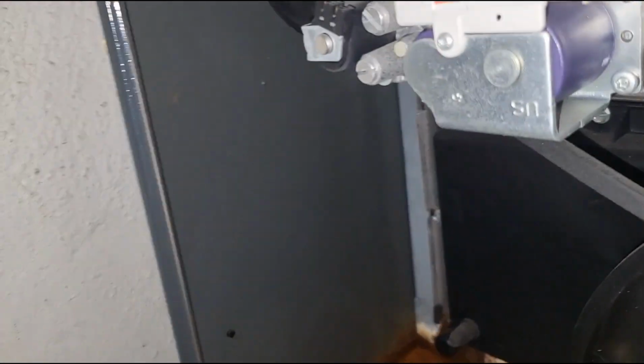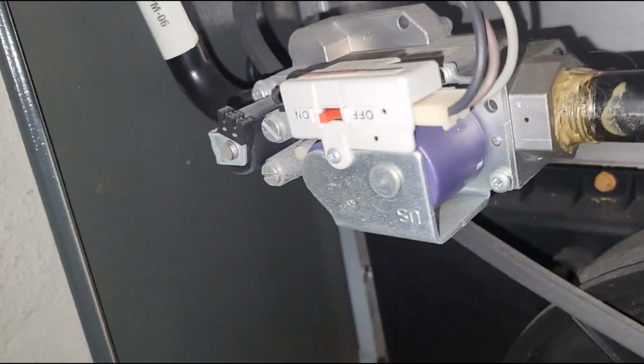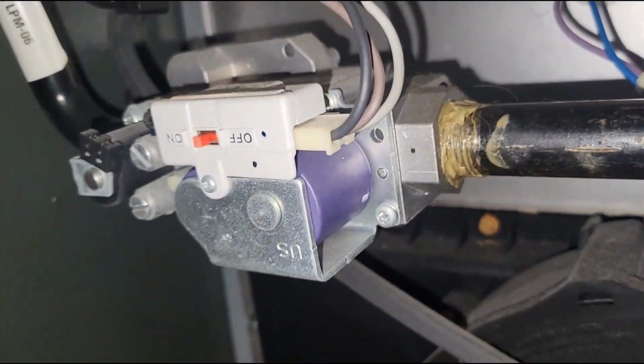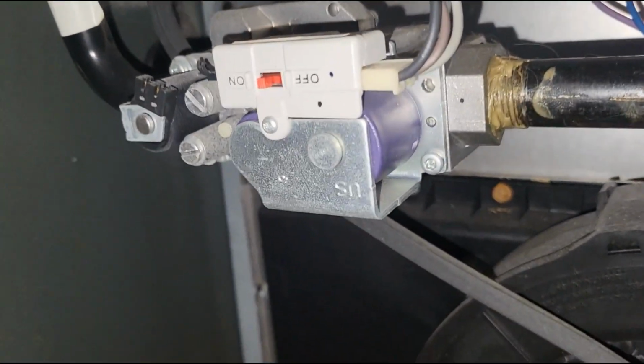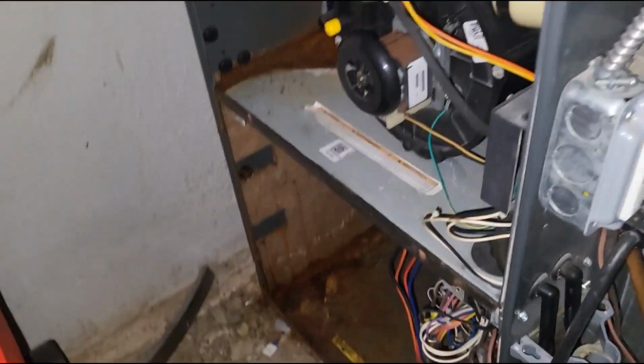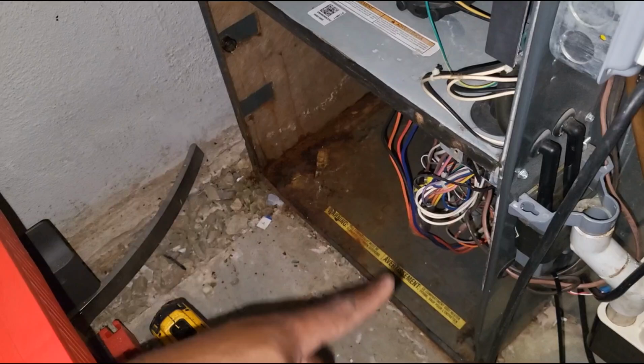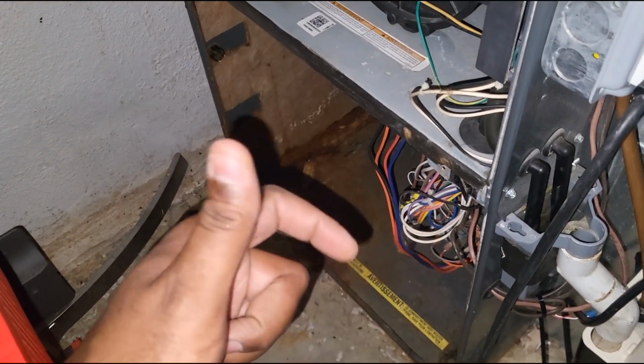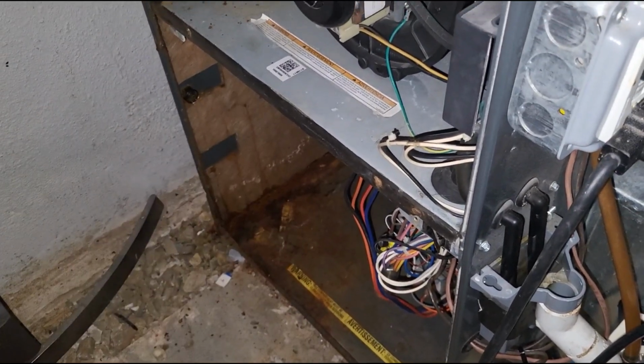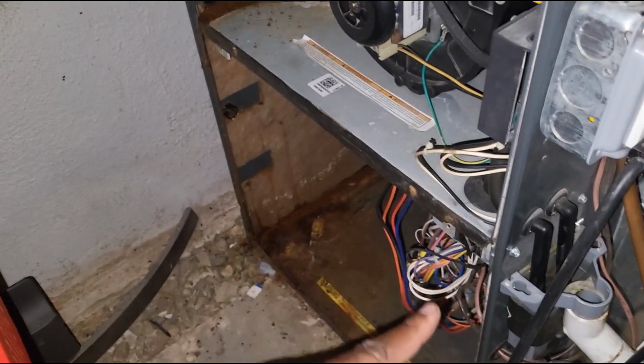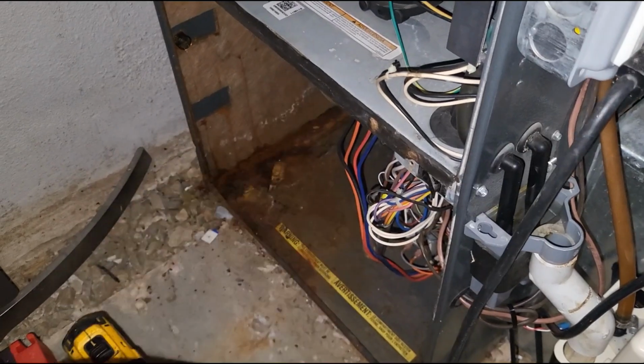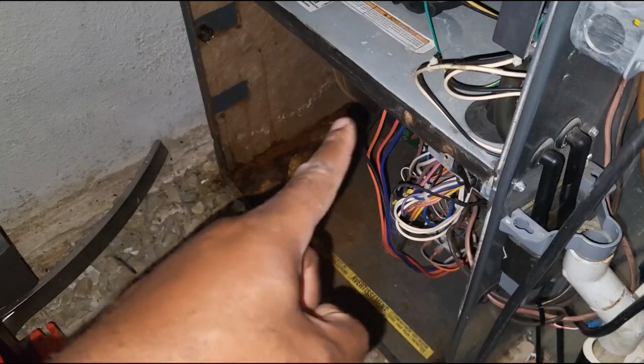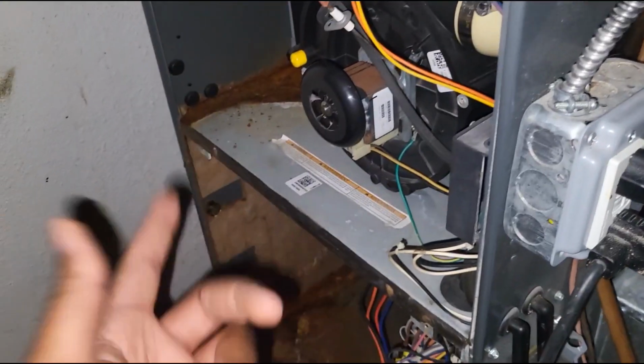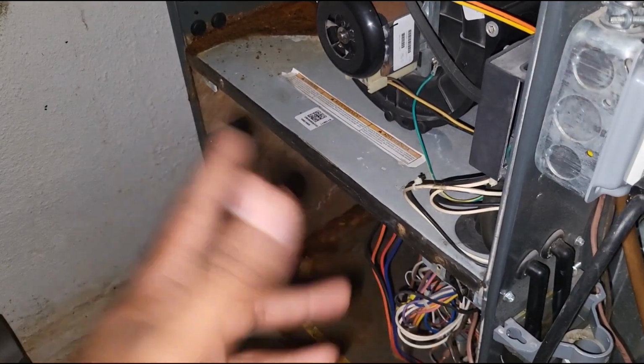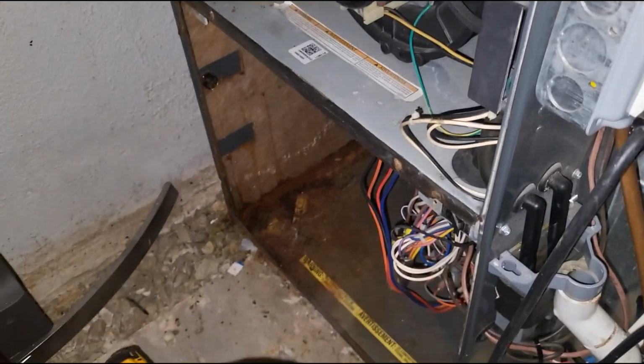And this looks very similar to the gas valve that I replaced last week. I don't know if this is a 2-stage 90%er, I think it might be. And guys, that's another thing with these Goodman 90% furnaces. Even if you get a 2-stage furnace, there's a dip switch on the circuit board. Let's say if you only want, for some reason, a 2-stage furnace to operate as a single stage, there's a dip switch you can switch on the circuit board to switch it from 2-stage to single stage. So now, instead of this unit modulating from first to second, like usually how most 2-stage furnaces operate, this furnace will only run on 1 stage.